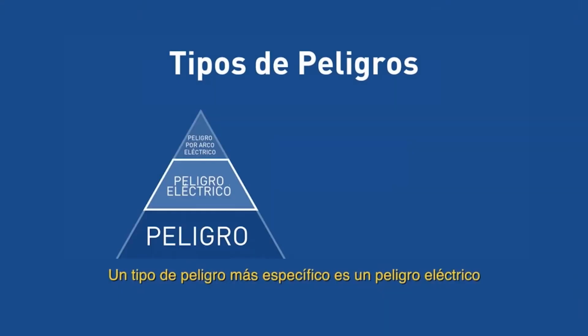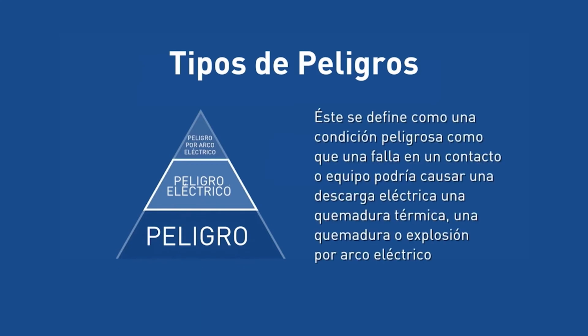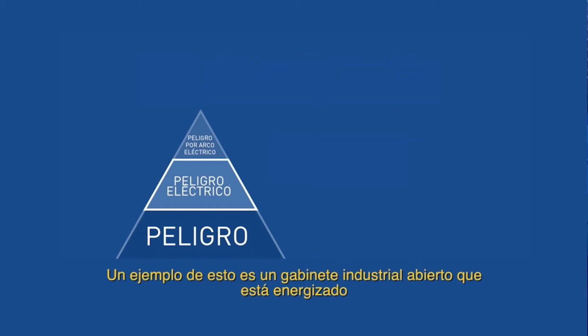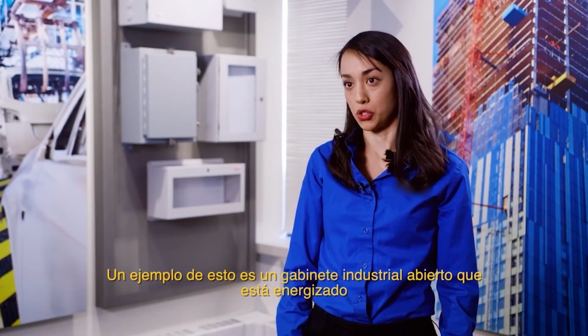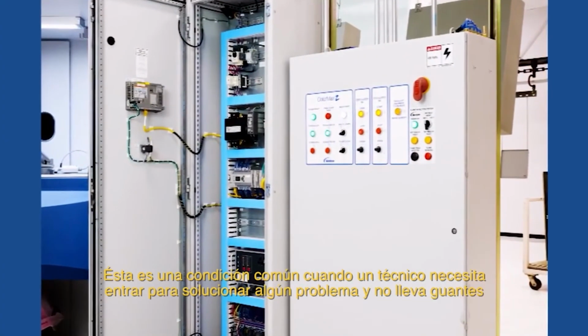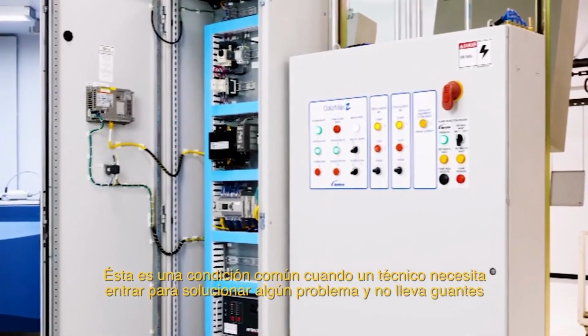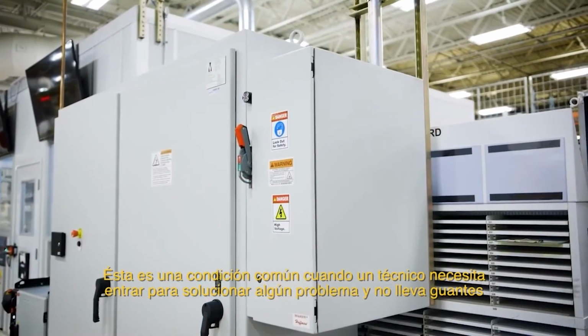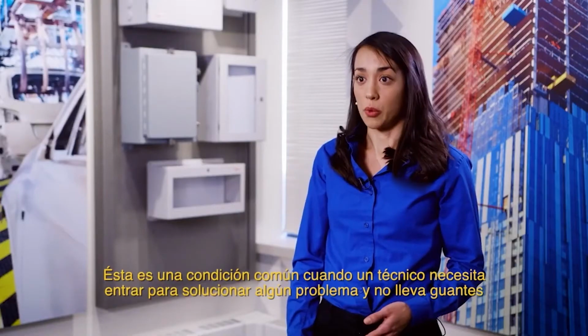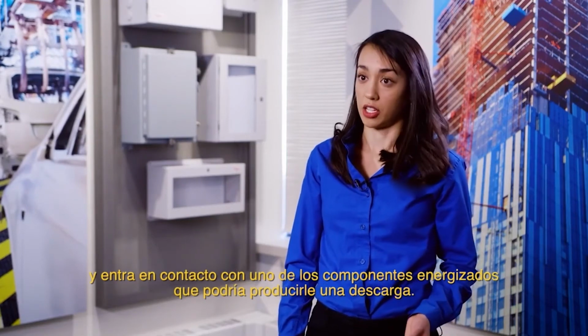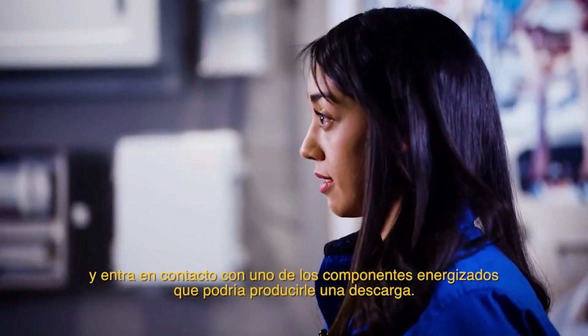A more specific type of hazard is an electrical hazard. This is defined as a dangerous condition such that contact or equipment failure could result in electric shock, thermal burn, arc flash burn, or blast. An example of this is an open industrial enclosure that is energized. This is a common condition when a technician needs to go in to work for troubleshooting purposes. And if he is not wearing gloves and comes into contact with one of the energized components, that could shock him.